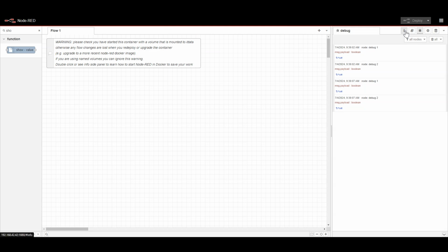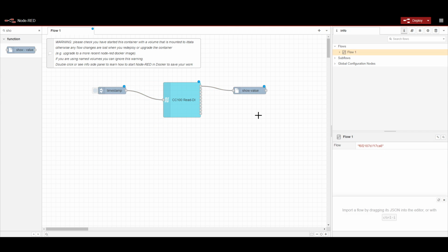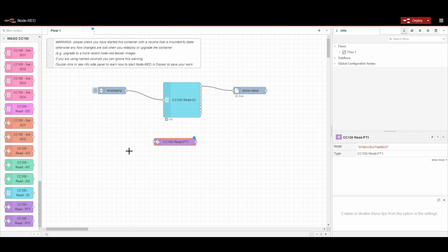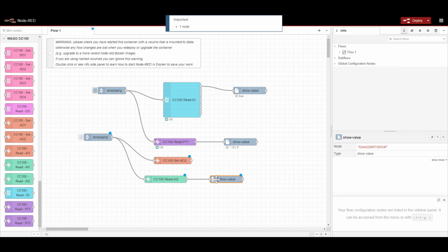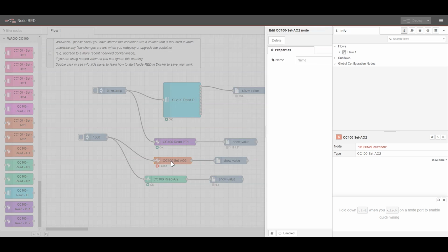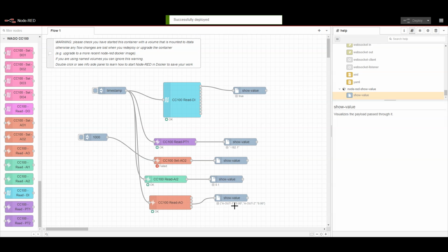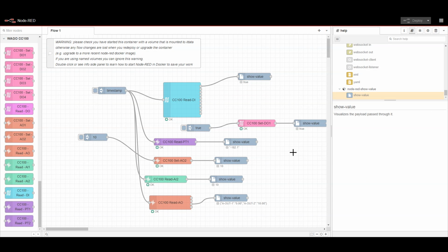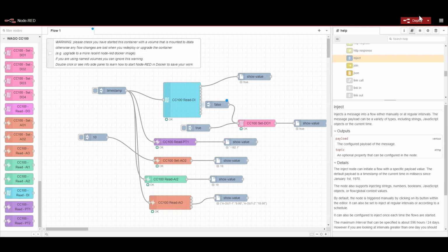Okay, once we install that for Wago, it comes with all the sets of IO boards. For example, read DI, which is 8, so 8 inputs coming directly into the node itself. Similarly, we can configure RTD, AI module, AO module, all of these using these nodes, and directly access the data from the Wago IO board. It allows us to interact directly, without using any CoDeSys or any different communication protocol. We get the data directly into Node-RED, and we can program our solution utilizing this.